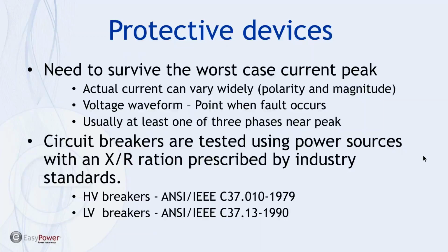So because the actual current can vary widely, and when we mean this, the DC offset is going to be different virtually every time we have a fault or every time we have an interruption in the current, and that is based upon the voltage waveform, and at the time and the phase that the fault occurs. So when the voltage is at 0 is when we have the maximum current, and depending upon whether it's going negative or going positive on the waveform will determine which direction, polarity-wise, the offset is affected. And usually, because we have a 3-phase system, all separated by 120 degrees, there usually is at least one of the phases that's near its peak contribution point, whereas the other two may be less so.